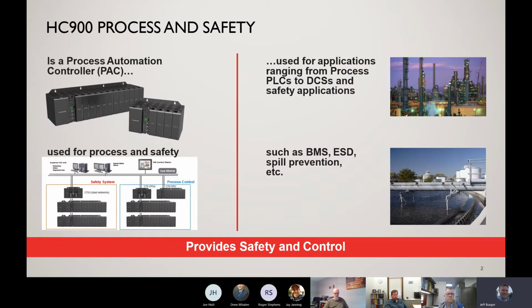We talked a little bit about the I/O and the CPU on the HC900. The HC900 has a capability of having SIL2 rated CPU and I/O. Most of the SIL2 rated systems are used in burner management systems, spill prevention, ESD, environmental type applications, and a lot of customers that require that SIL2 will move in that direction. It seems today more and more applications are requiring the SIL2, especially if you get into chemical, wastewater, refineries, things of that such, which requires a little bit different level or a higher level of security. Most customers will tell you that they're either requiring SIL2 or SIL3. Most of our applications are in the SIL2 rating.